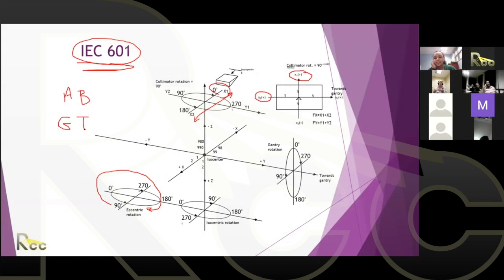Or you have to be very clear. You say in clinical mode, X1 needs calibration. I really don't know why Elekta, the newest version of Elekta, did this. The older version of Elekta, the precise series, the ones before that, there was no problem. So you'd be in the same coordinate system between service and clinical. But with the Versa, they switched for some reason.